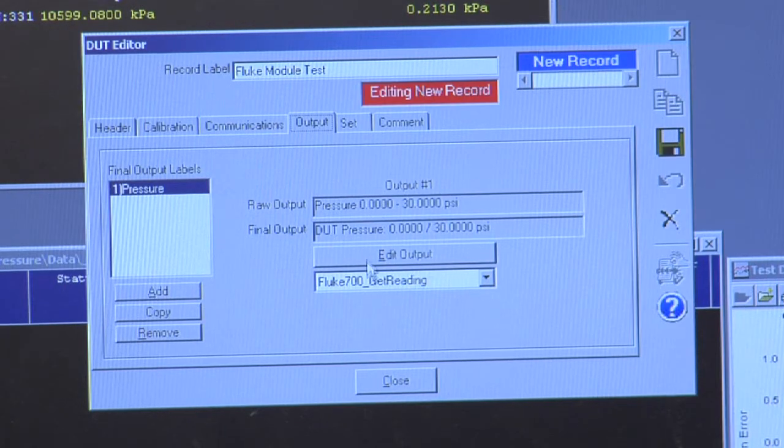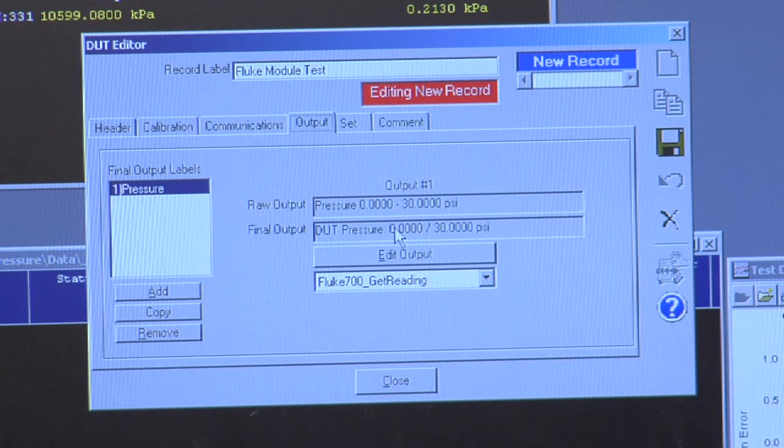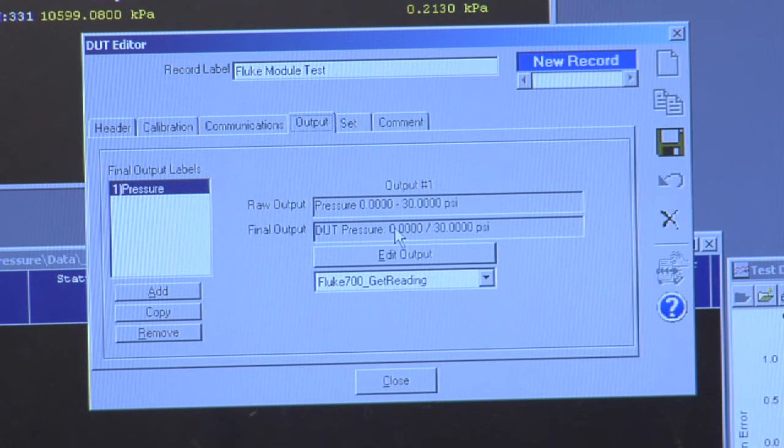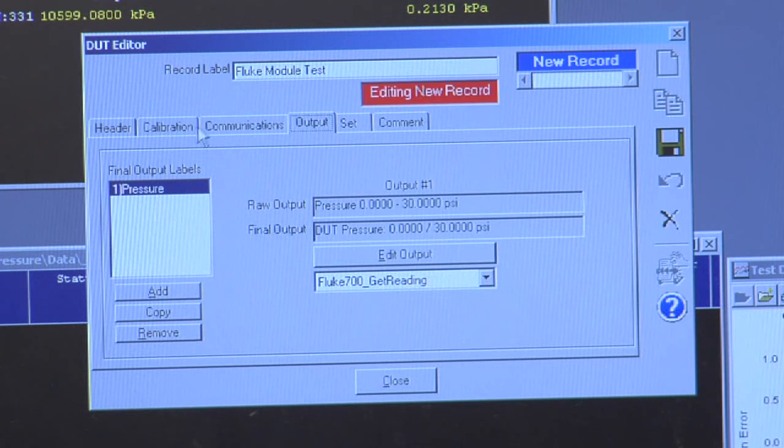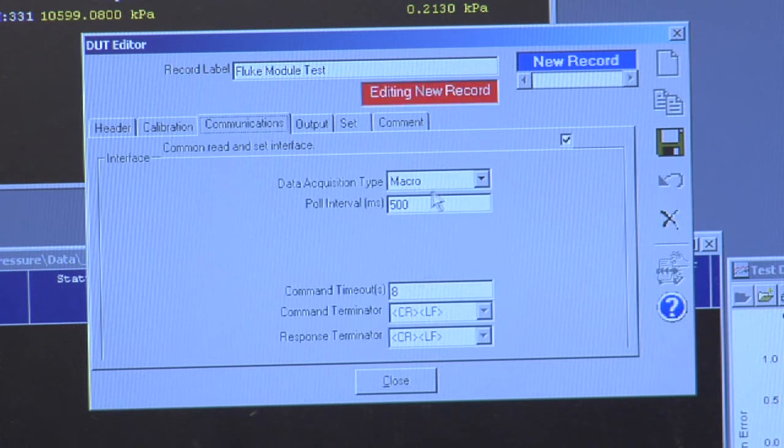The pressure module is actually a complicated instrument. It's one of very few instruments that you have to actually use a separate program for communication. So in this case, communications is defined by a macro.